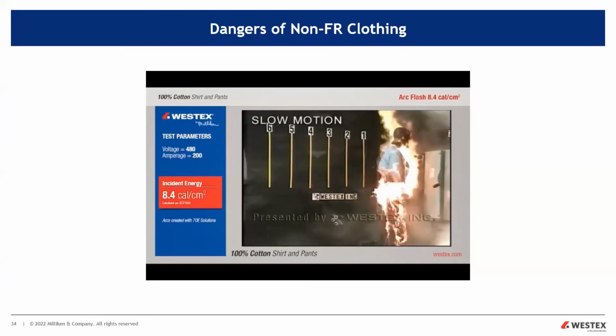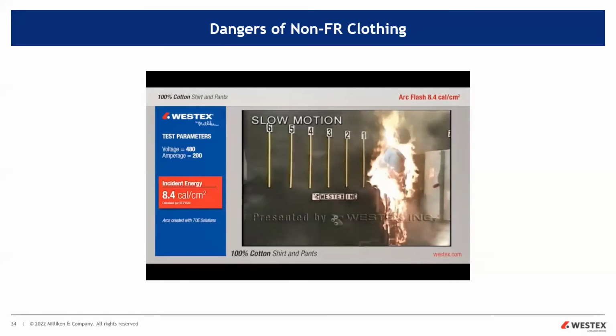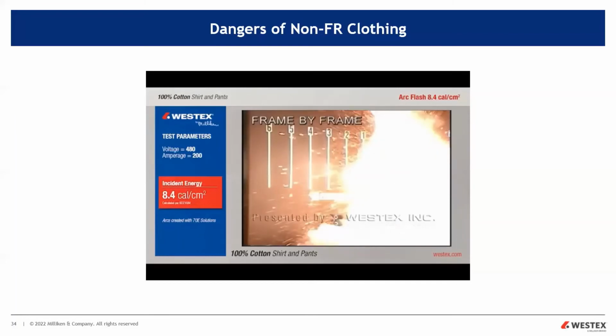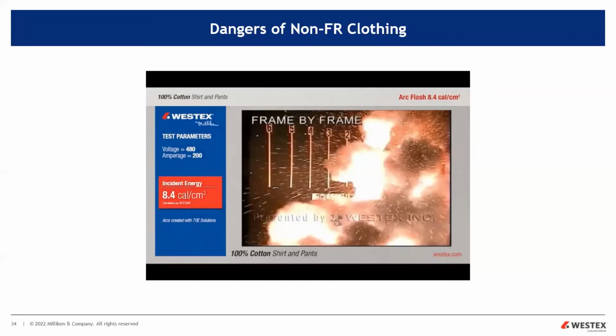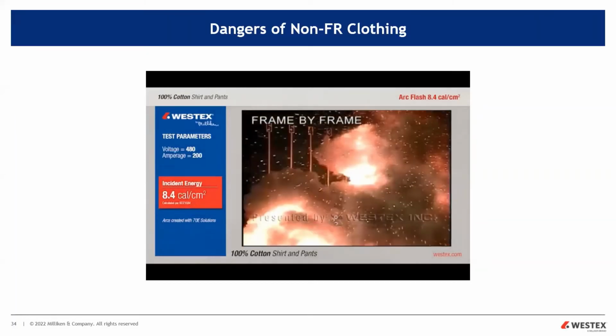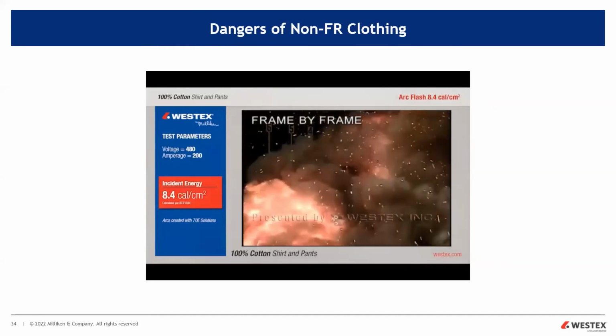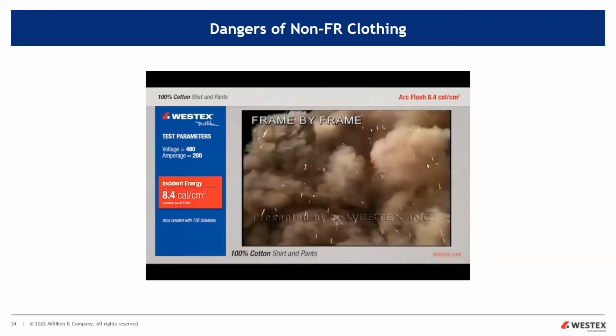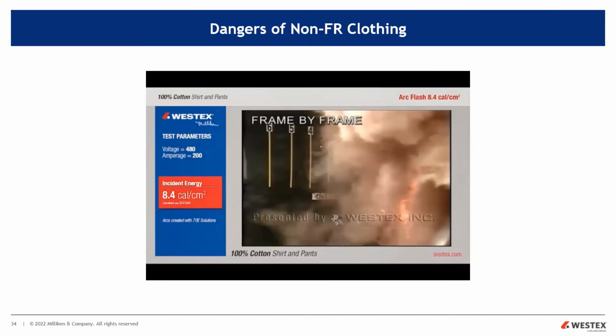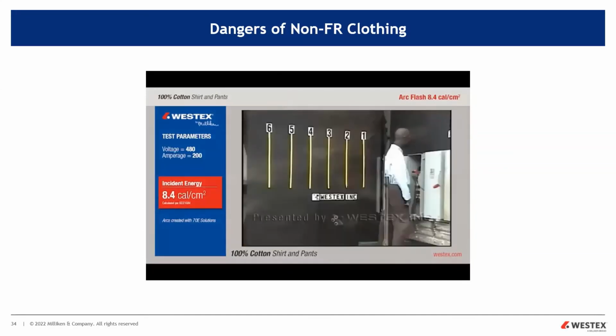Head to toe. 70E requires head to toe, well known. In frame by frame, coming up shortly, we'll get another very close look at this arc. You can see that after the second cycle or so, it's on the ground and a great distance from the arc gap, completely enveloping the mannequin, putting out a large amount of molten metal, and again, causing the fire. So obviously cotton's not an upgrade for your electrical personnel. And if they don't put the task-based PPE on, you could have this incident.